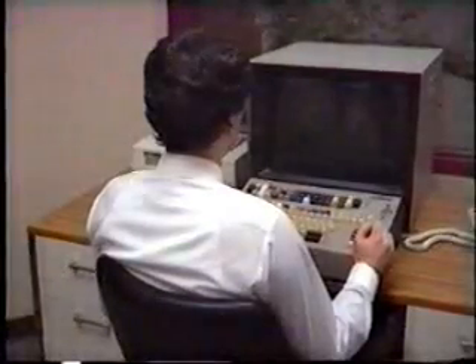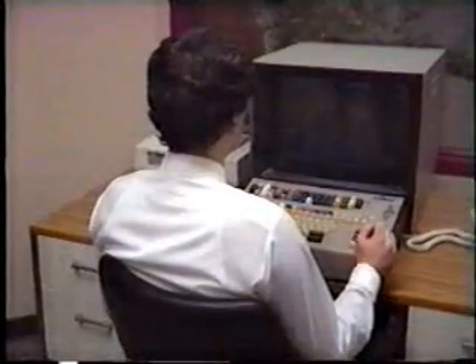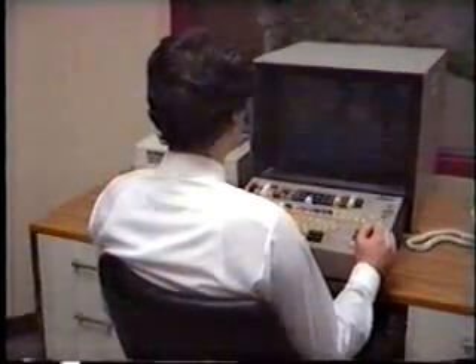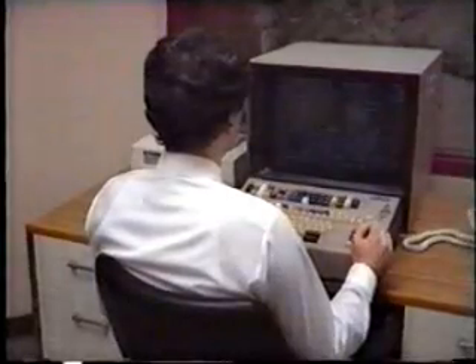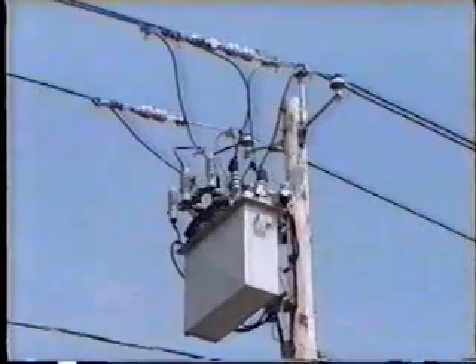This effect is more noticeable on loop-connected systems rather than on radially connected distribution lines. Normally, fault studies are carried out by your company's engineering department to provide maximum and minimum levels of fault expected at each location. When setting the time dial, we have to take into consideration the minimum level of fault current at the end of the line. We do not want this fault current to flow for an extended period of time and cause damage.